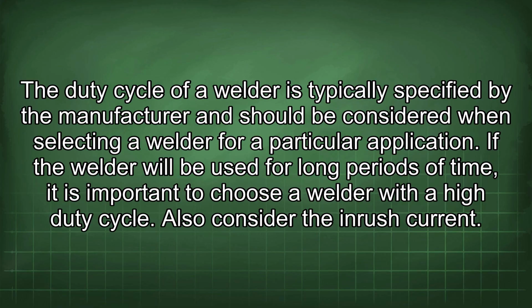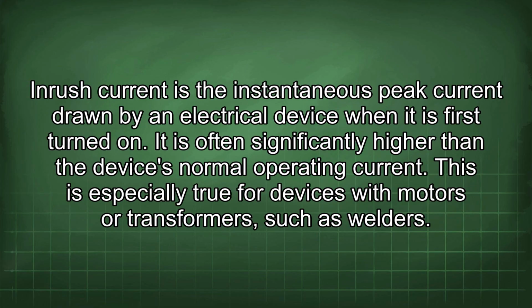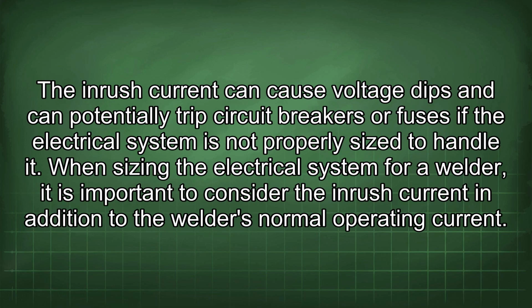Also consider the inrush current. Inrush current is the instantaneous peak current drawn by an electrical device when it is first turned on. It is often significantly higher than the device's normal operating current. This is especially true for devices with motors or transformers, such as welders. The inrush current can cause voltage dips and can potentially trip circuit breakers or fuses if the electrical system is not properly sized to handle it.